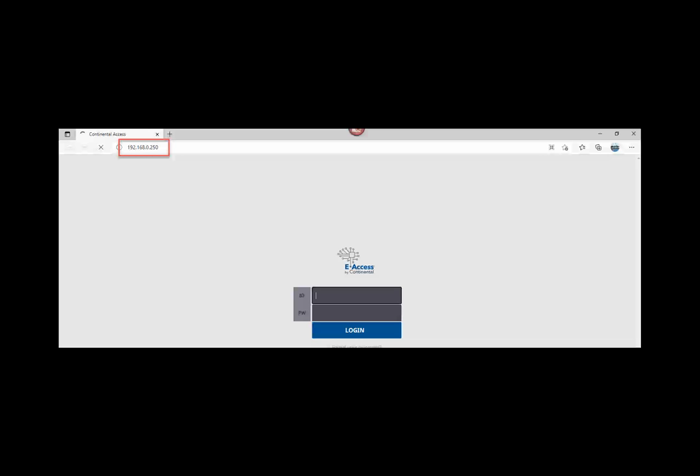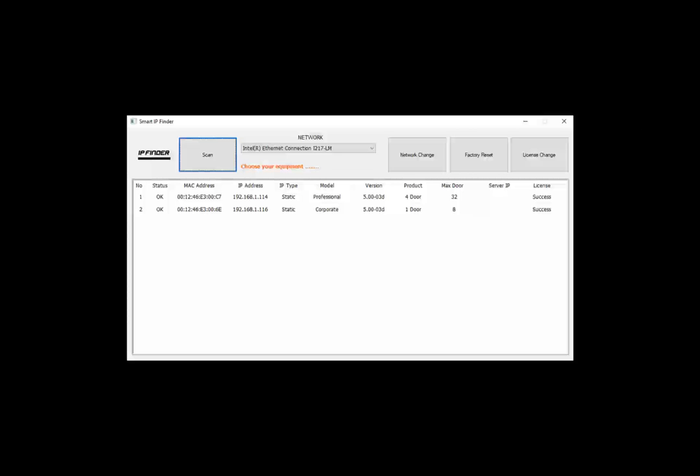If you are unable to access the controller using a browser, the second method would be to download the Smart IP Finder utility from the Continental Document Library. The Smart IP Finder utility is used to search for the eAccess controllers. Install the Smart IP Finder utility on the computer that is connected directly to the controller. Click Scan. Upon searching and finding your controller, you can use the Smart IP Finder utility to program in a static IP address into the controller that meets your network address scheme.